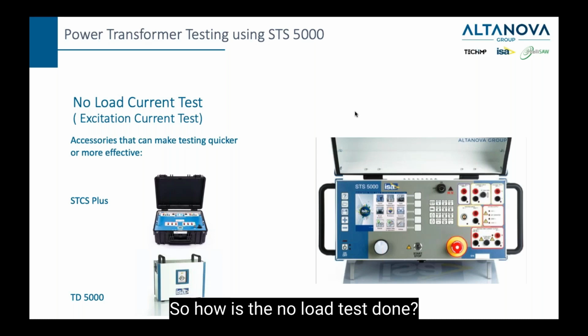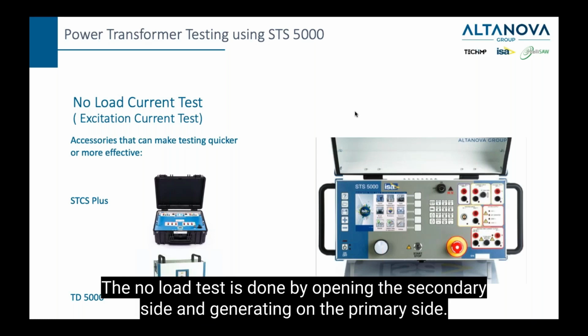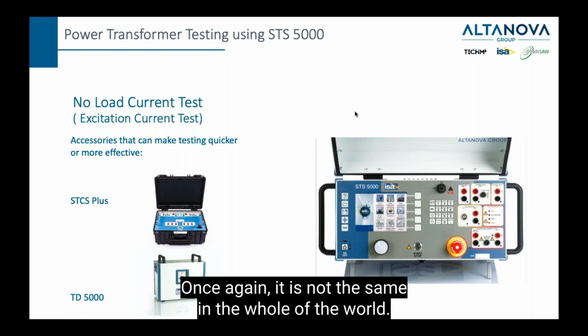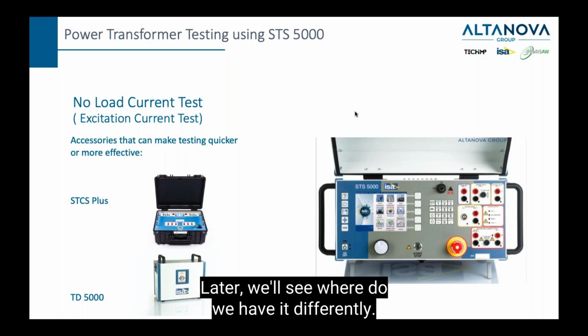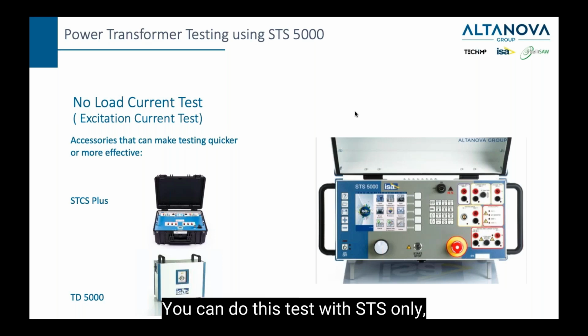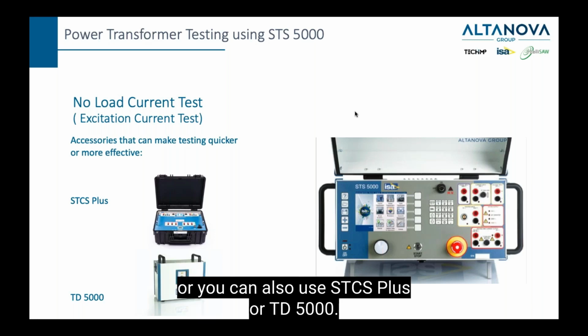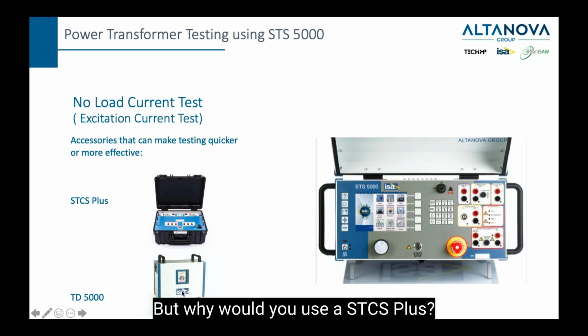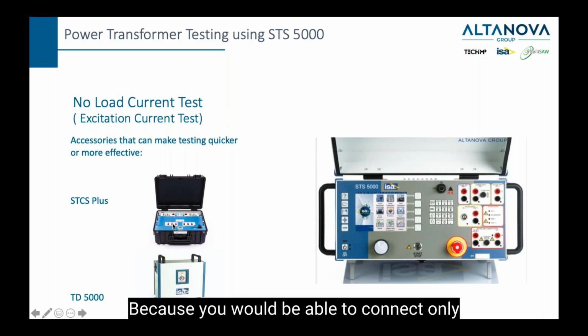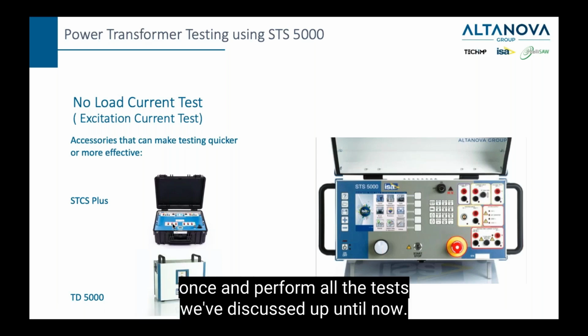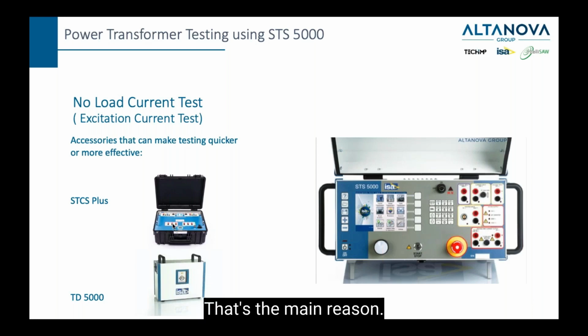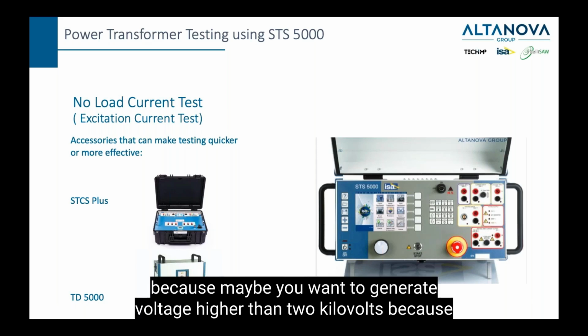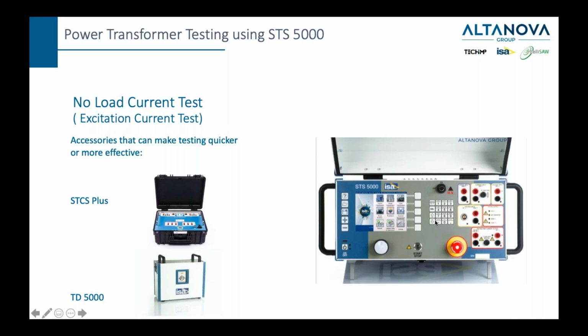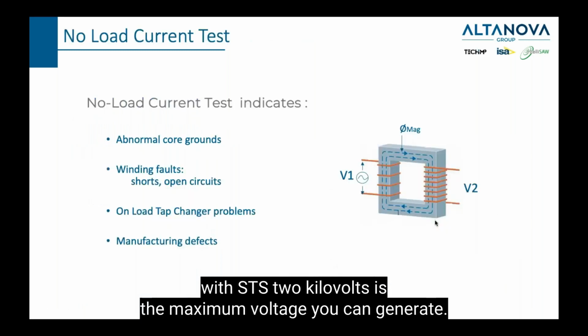So how is the no load test done? The no load test is done by opening the secondary side and generating on the primary side. Once again, it is not the same in the whole world. Later we'll see where we have it differently. You can do this test with STS only, or you can also use STCS Plus or TD5000. You cannot use both of them, but why would you use STCS Plus? Because you would be able to connect only once and perform all the tests we've discussed up until now. That's the main reason. And the TD5000 you would use because maybe you want to generate voltage higher than 2 kilovolts, because with STS, 2 kilovolts is the maximum voltage you can generate.